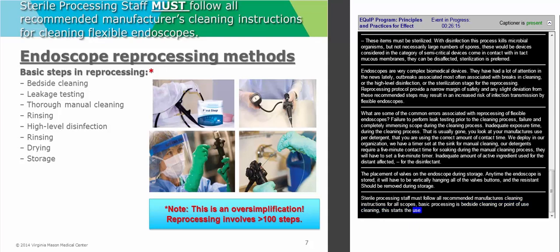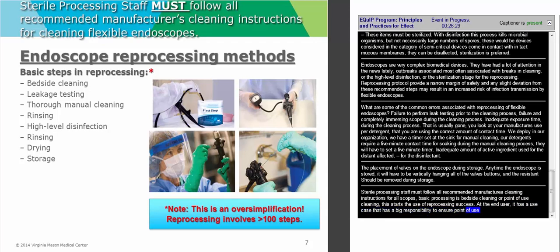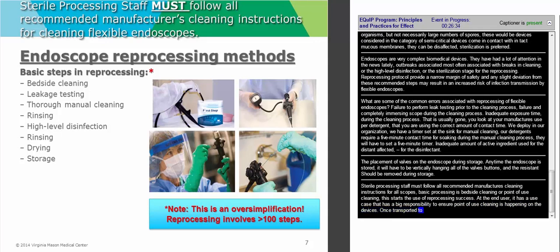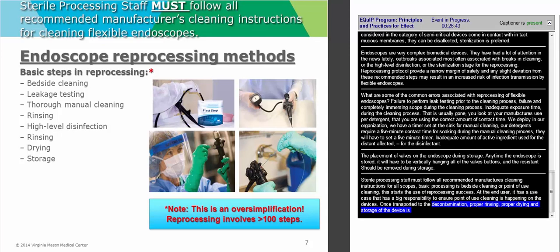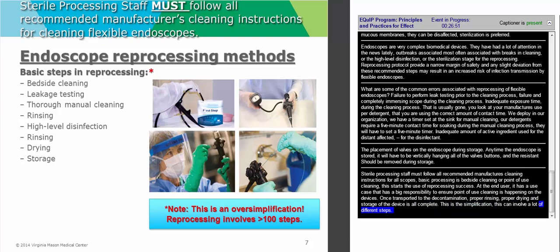I believe that the end user does have a big responsibility, whether it be in the clinics or in the OR, wherever these devices are being used, that point-of-use cleaning is happening on these devices. Once it's transported to the decontamination area, proper leak testing, thorough manual cleaning, rinsing, the high-level disinfection process, again rinsing, proper drying, and storage of the device is all completed. Note that this is an oversimplification. This could involve a lot of different steps, and we could hang our shingle just on this slide alone and do a whole other presentation on cleaning of flexible endoscopes and this process.